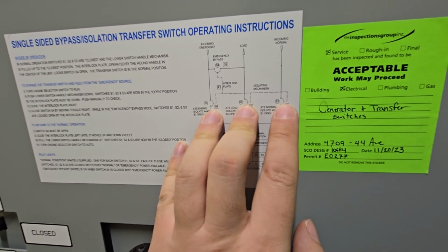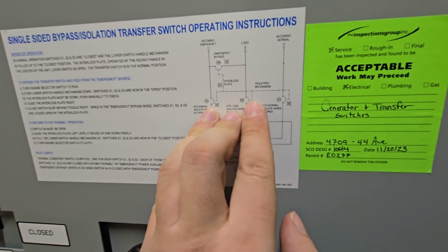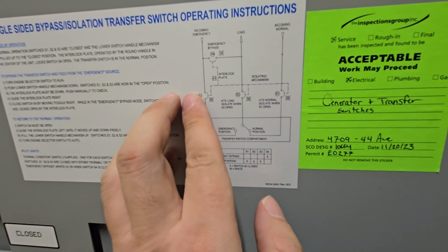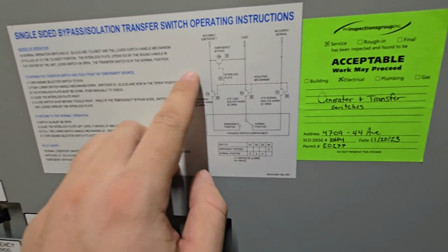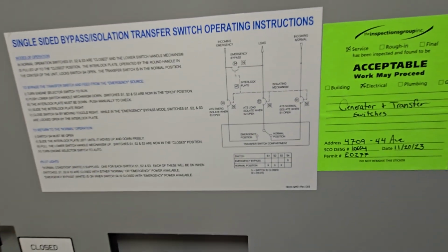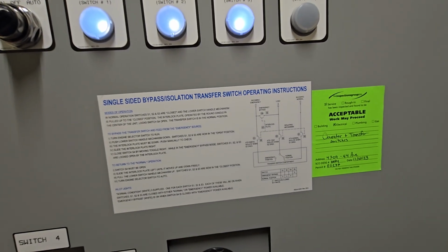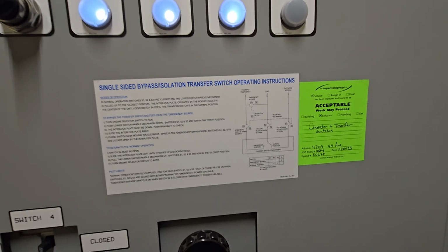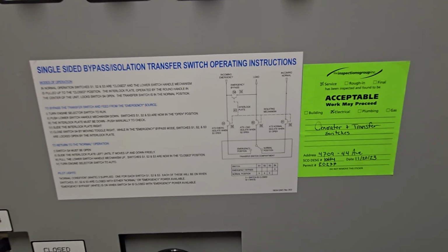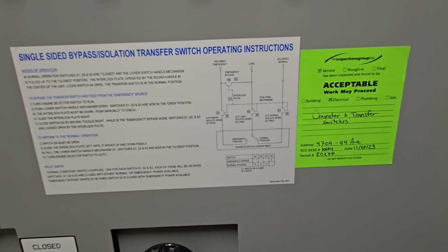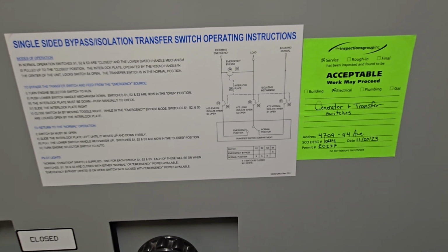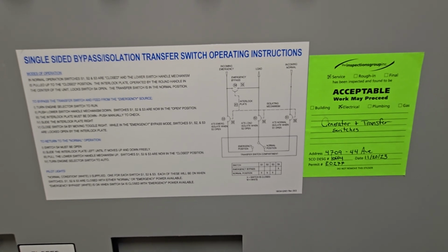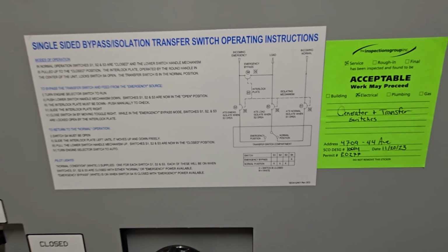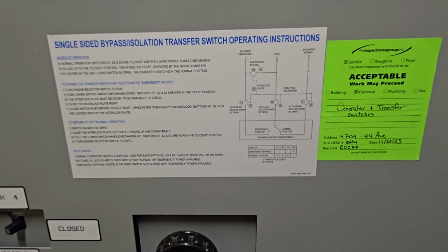So it disconnects us from everything, from the utility, from the load, which is our building, and from the generator power. The reason we disconnect everything is we don't want to have an arc flash. We want to make sure there's no power coming in at all into the building before we activate the generator. Otherwise we'd have a huge explosion.